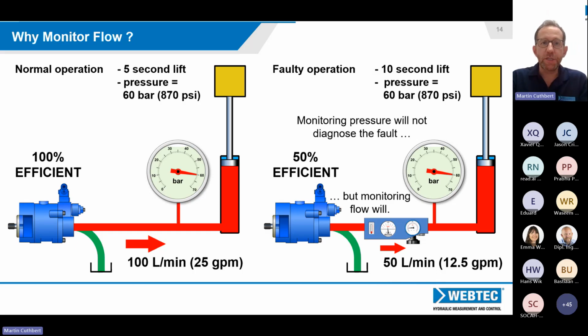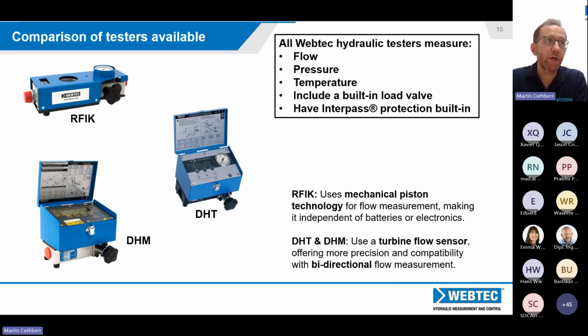Let's expand a bit on the different types of test equipment available. Here are three different ranges of testers that WebTec manufactures. Top left is the RFIK, an all-mechanical unit with literally no batteries, using pressure drop to move a piston against a spring to measure flow, with a thermometer, pressure gauge and load valve. The DHT and DHM are both turbine-based testers with electronics and a battery, with different amounts of digital display - the DHM is all digital, and the DHT is part digital, part analog.